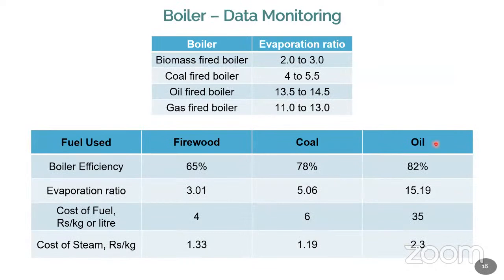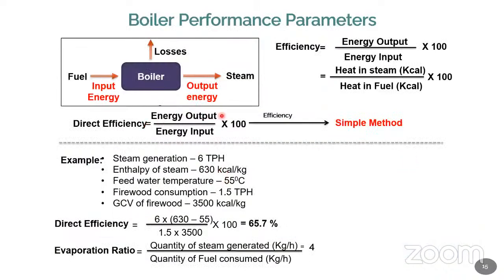Then the second parameter is efficiency. Efficiency calculation is again a very simple one: the energy output divided by the energy input, multiplied by 100. So what is the energy output? It is the heat content in the steam, and the heat content in the fuel can be represented in terms of kilocalories, and again fuel content in kilocalories, multiplied by 100.